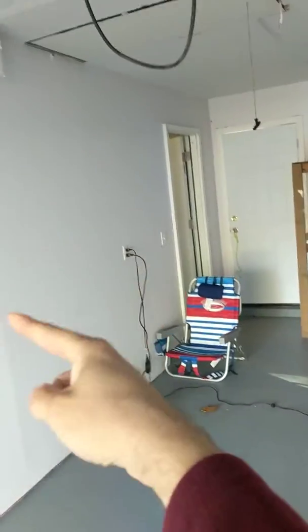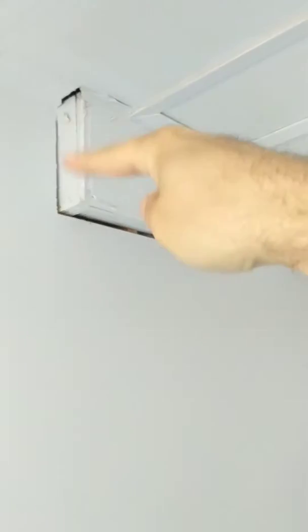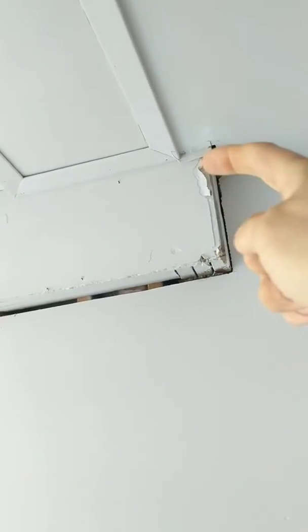Issues with the garage. This is an adjacent wall to a living space. That means anything on this wall has to be fire blocked. So option one is to sheetrock this with 5/8 sheetrock, corner and spackle it, or which is going to be easier, is to get the orange fire spray foam all this stuff right here.